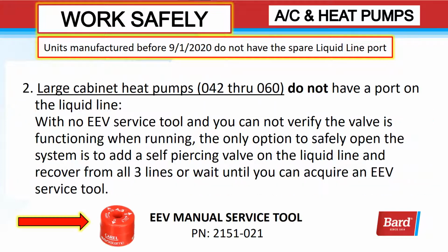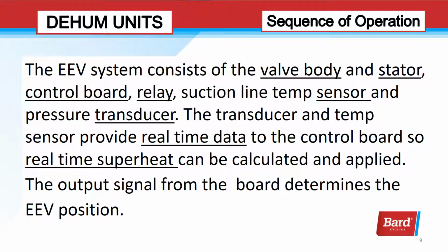The second group is the large cabinet heat pumps, and that would be the W42 through W60H units, and those do not have a port on the liquid line. With no EEV service tool and you can't run the equipment and verify the valve is functioning to turn the power off, the only option to safely open the system up is to add a self-piercing valve on the liquid line and recover from all 3 lines, or wait until you can acquire an EEV service tool. The EEV system consists of the valve body, stator, control board, relay, temperature sensor and transducer on the suction line.